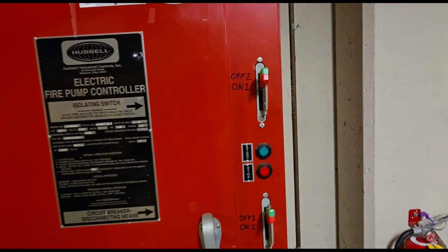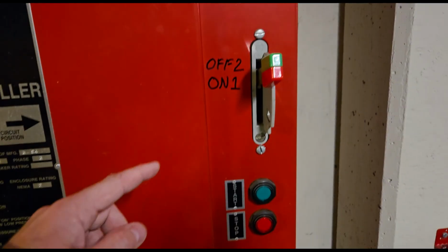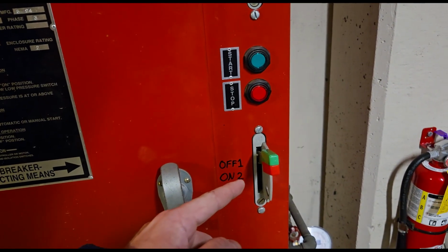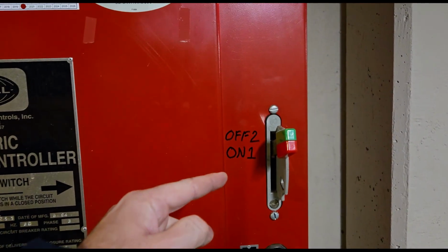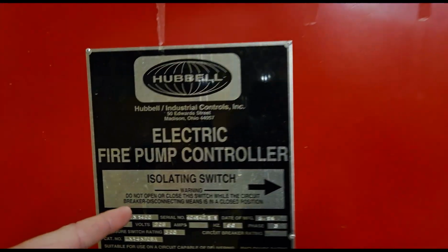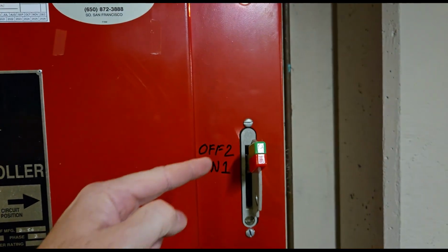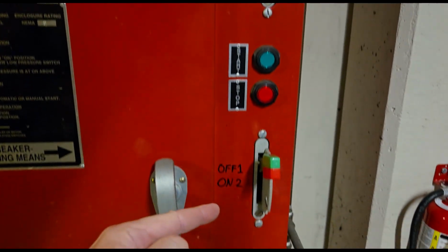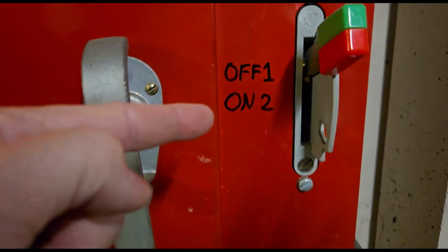Once that's good, then we'll turn these switches or levers back on. And instead of doing this one on first because we turned it off first, we're actually going to turn this one on first, so this is the isolating switch. So we're going to turn the isolating switch on first, and then the circuit breaker on second. So you see on two.